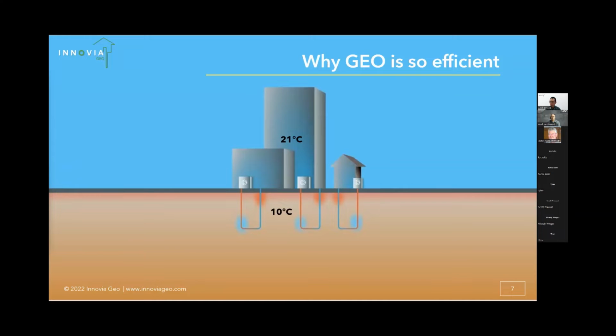The way to think about it is similar to pumping water up a hill: the higher it is, the more energy it takes to pump that water there. The same principle applies with a heat pump, because we're pumping heat from one place to the next. If our target is 21 degrees Celsius, kind of room temperature, in the wintertime we're using geothermal, where the ground is around 10 degrees Celsius. It's a lot easier to get heat from that 10 degrees Celsius and pump it into the building than it is from the outside air if it's minus 20 on a cold winter day.